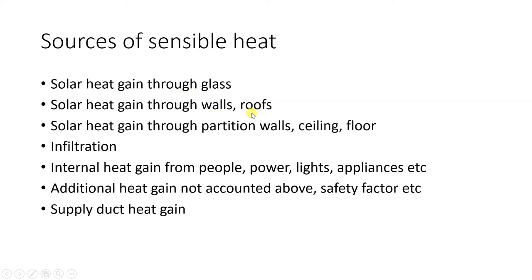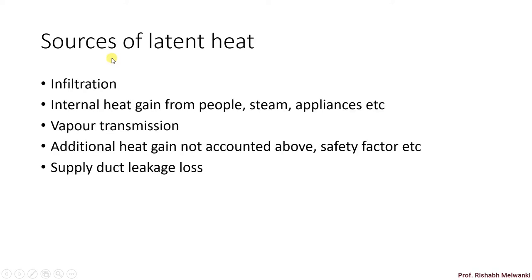Sources of sensible heat include glass, wall, roof, partition wall, ceiling floor, infiltration, and internal heat gain from people, power, lights, appliances, and additional heat gain using a safety factor. Sources of latent heat include moisture content. For human beings there will be perspiration and sweating. Infiltration air will also have moisture content. If steam is present due to some process, that steam will form the latent heat load, along with vapor transmission.